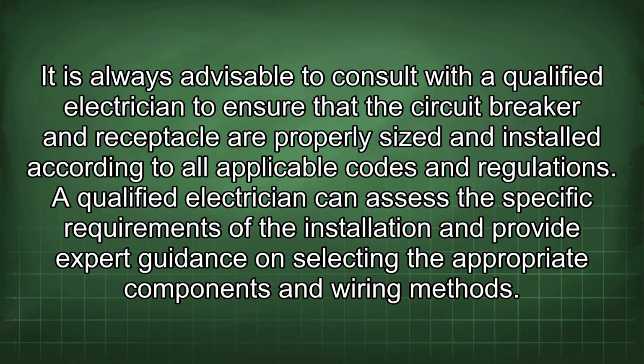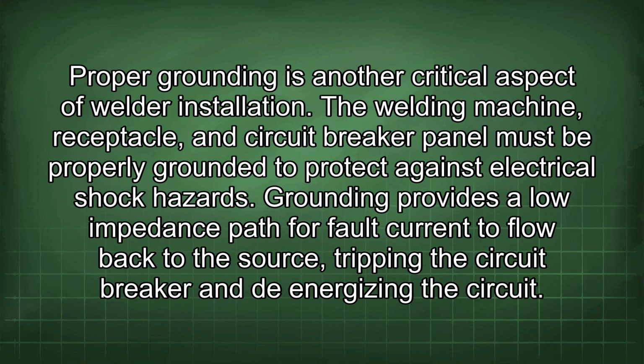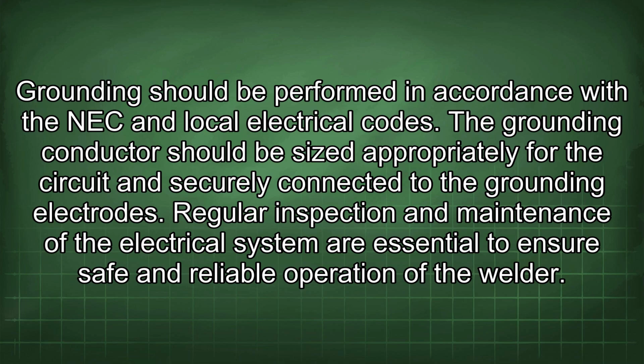These recommendations should be carefully considered when selecting the appropriate circuit protection and connection components. It is always advisable to consult with a qualified electrician to ensure that the circuit breaker and receptacle are properly sized and installed according to all applicable codes and regulations. A qualified electrician can assess the specific requirements of the installation and provide expert guidance on selecting the appropriate components and wiring methods. Proper grounding is another critical aspect of welder installation. The welding machine, receptacle, and circuit breaker panel must be properly grounded to protect against electrical shock hazards. Grounding provides a low impedance path for fault current to flow back to the source, tripping the circuit breaker and de-energizing the circuit.